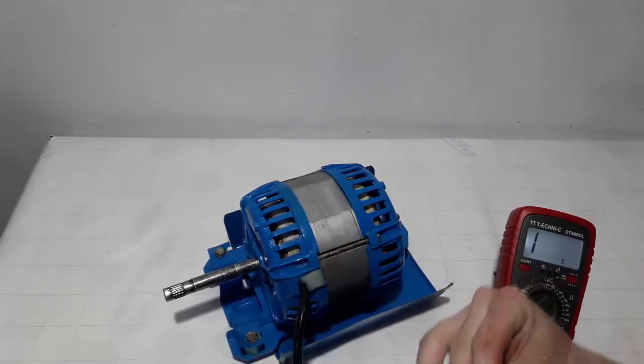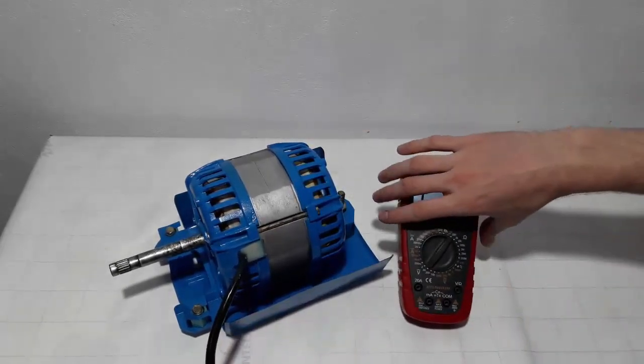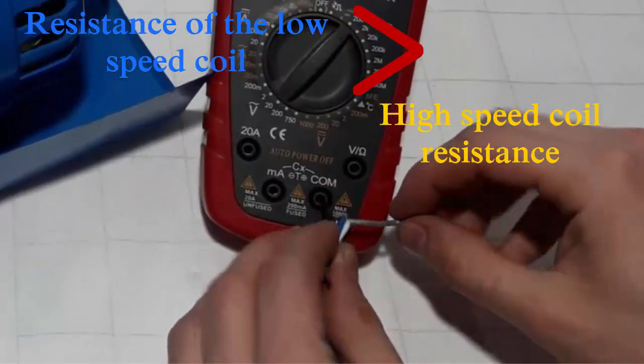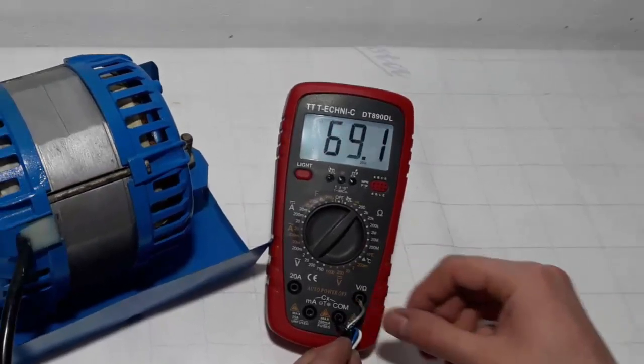How can we identify these wires? It's easy. We need just to measure resistance by multimeter. First, we look for the two coils: low speed coil and high speed coil. As you know, the first one has a higher resistance than the second.